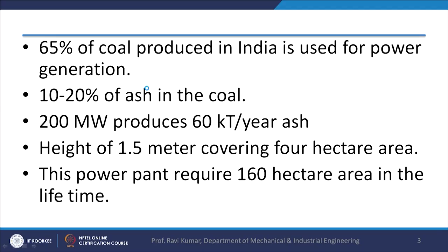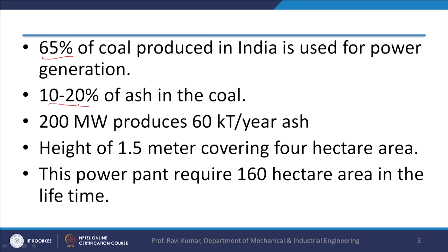Ash is the unburned part of the coal which remains in the power plant and has to be disposed. Disposal of ash is now a big issue in thermal power plants. 65 percent of coal production is used for power generation in India, approximately two-thirds. Coal may contain 10 to 20 percent ash; very high grade coal may contain 5 or 6 percent ash, but normally coal used in power plants contains 10 to 20 percent ash.